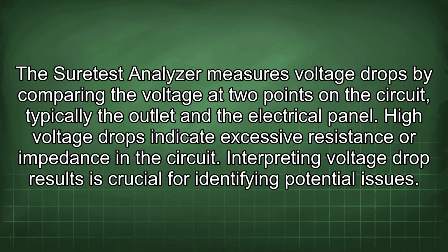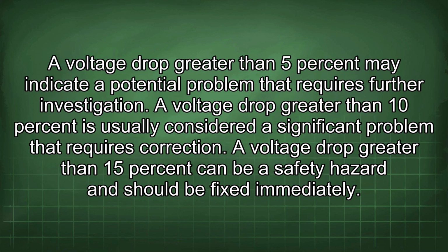Interpreting voltage drop results is crucial for identifying potential issues. A voltage drop greater than 5% may indicate a potential problem that requires further investigation. A voltage drop greater than 10% is usually considered a significant problem that requires correction. A voltage drop greater than 15% can be a safety hazard and should be fixed immediately.